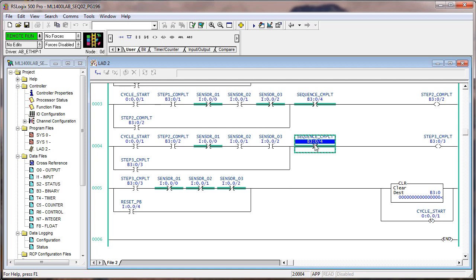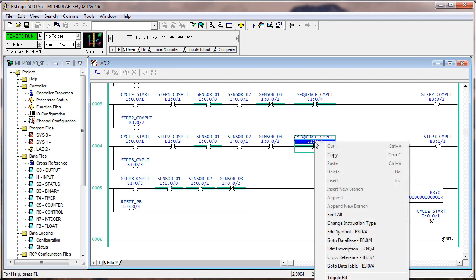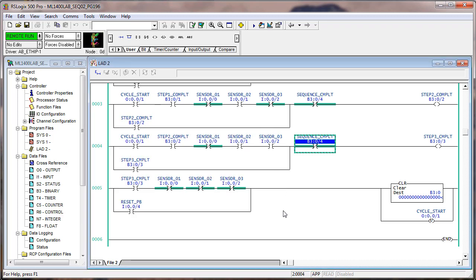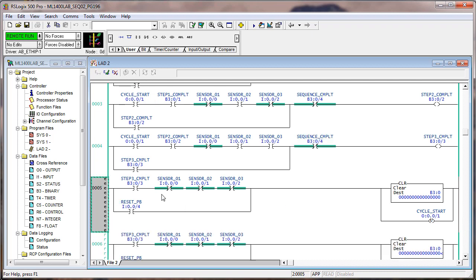So I right-clicked on sequence complete and I did a cross-reference to show you that there's an XIO, true if off, in rungs 0, 2, 3, and 4, but there's no OTE. There's nothing turning it on. So let's do something to turn on sequence complete. Now we no longer have to clear B30 because we're not latching these bits anymore. We don't have to unlatch cycle start because we're not latching it.